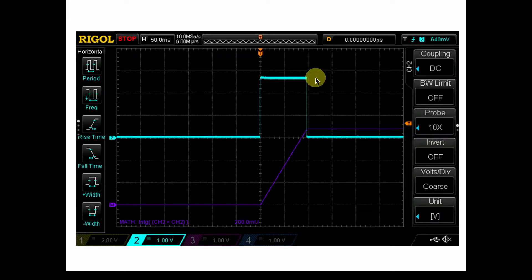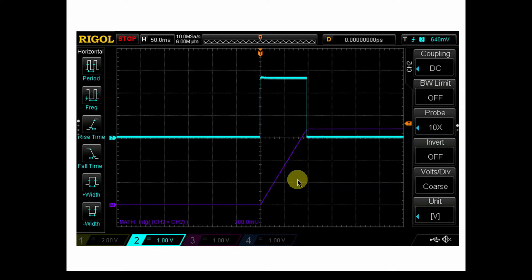So we're going to figure out how you can calculate I squared T from a current through a device. For example, you might have a pulse like this, a pulse of current, and this one is 100 milliseconds pulse. We're going to see if that is sufficient or getting near the rating of the fuse so that might give you enough energy to melt the fuse. And here in this blue is what we're going to be calculating. It's basically going to be calculating for this pulse, the increasing amount of energy that is going through that fuse just for this pulse. It's going to build up and build up, and when the pulse stops, you're going to have a fixed amount of energy.